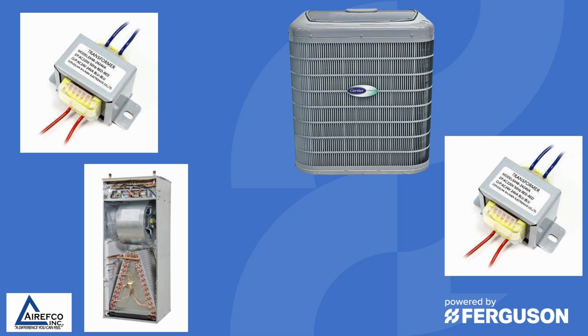Now, if the transformers are phased together correctly, it really wouldn't make any difference if you wired it into the outdoor unit, because then the transformers would work together instead of against each other. But if they were incorrectly phased, then one of the transformers, either the indoor or the outdoor, would fail after a period of time because of the voltage being generated by the improper phasing. So always keep in mind, if you have a 2-transformer system, they should be kept separate.